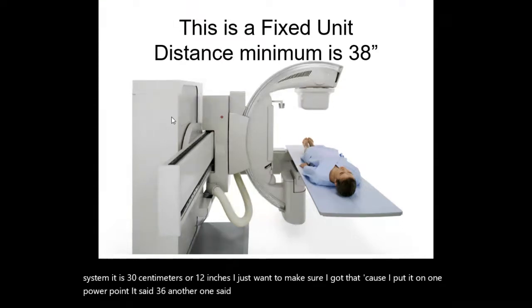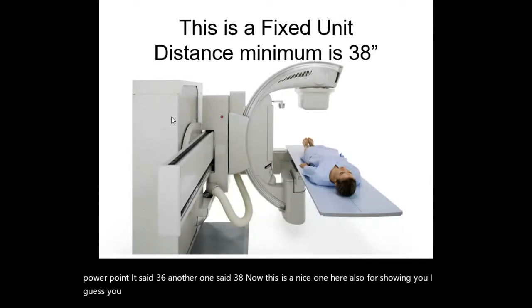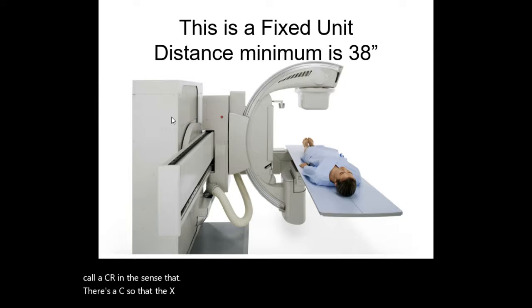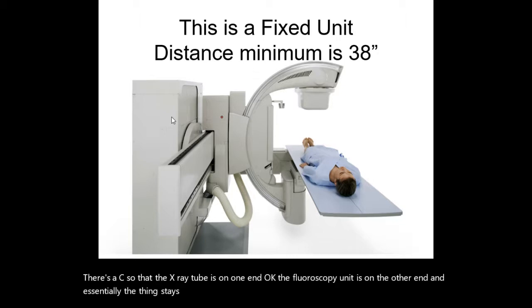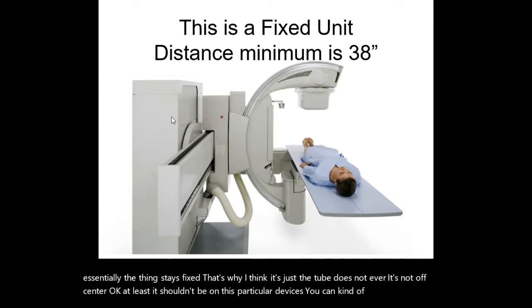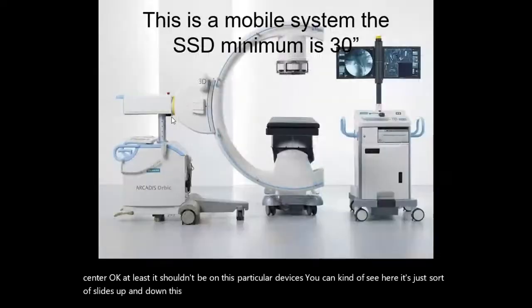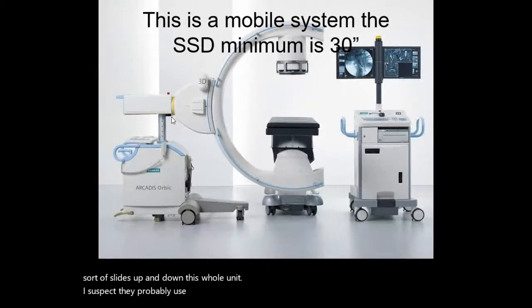Now, this is a nice one here also for showing you the construction of a fluoroscopy unit. This is what we call a C-arm in the sense that you see there's a C, so that the X-ray tube is on one end, the fluoroscopy unit is on the other end, and essentially the thing stays fixed. That's why the tube is not off center, or at least it shouldn't be. On this particular device, as you can see here, it just slides up and down this whole unit. I suspect they probably use something like that with interventional.